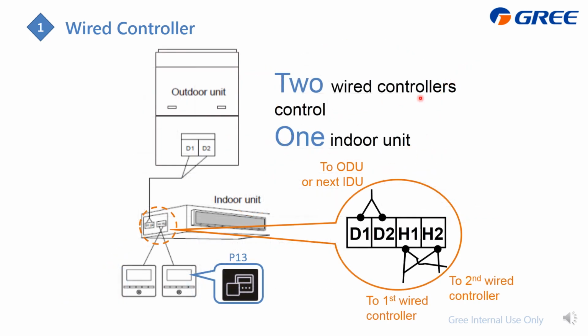Two wire controllers controlling one indoor unit: for the wiring, you need to connect these 2 wire controllers to the same indoor unit, the same H1, H2 together. Also select either one of these wire controllers as the master, which is done by changing P13.